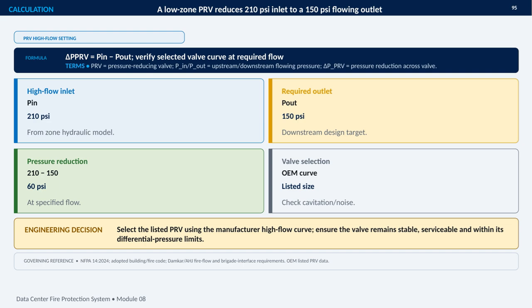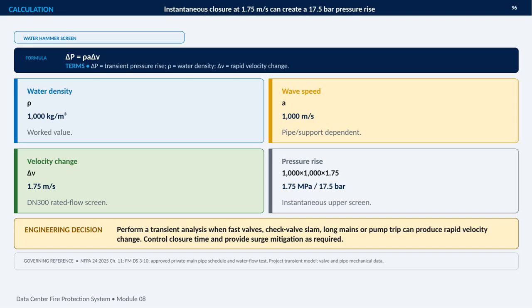This slide screens the potential water hammer pressure rise caused by an instantaneous closure. The governing relationship is delta P equals rho times A times delta V. Pressure rise depends on water density, wave speed, and the rapid change in flow velocity. Using the worked values shown here, water density is 1,000 kilograms per cubic meter, wave speed is 1,000 meters per second, and the velocity change is 1.75 meters per second, based on the DN 300 rated flow screen. Multiplying those terms gives 1.75 megapascals, or 17.5 bar of pressure rise.